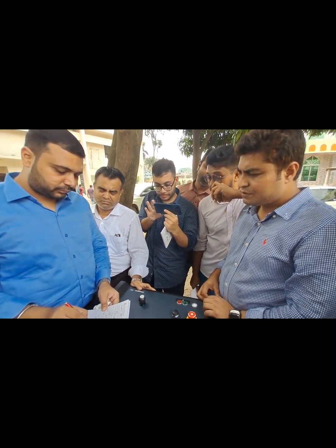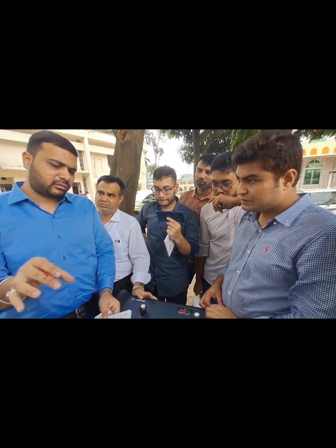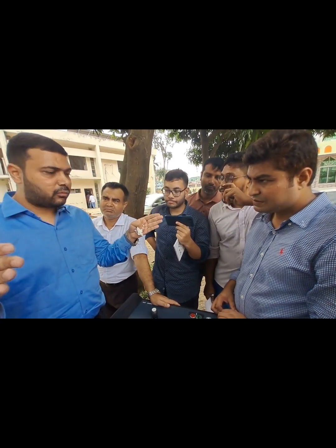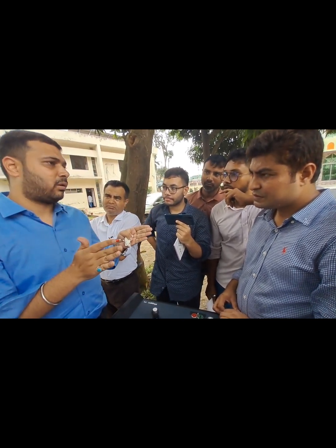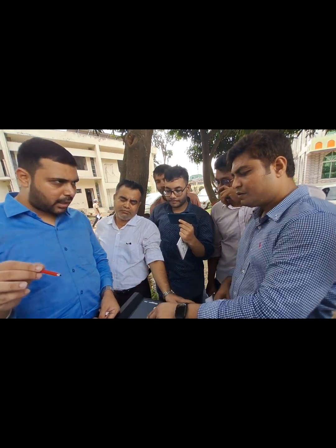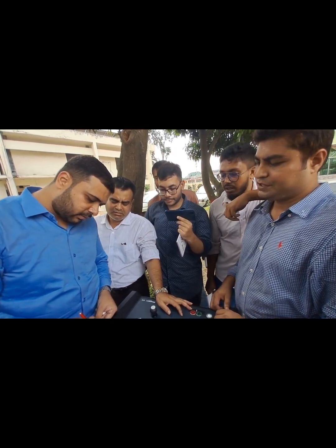This is the pre-locating method. Now I consider that this core is faulty. What is the total length of the cable? Where is the exact fault? So how can you come to know? This is the method: the Arc Reflection Method. Arc means arc, and reflection method.